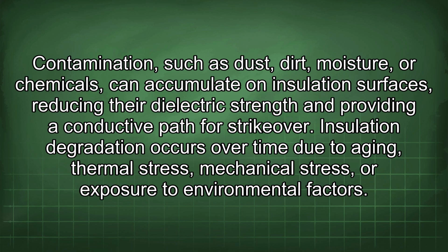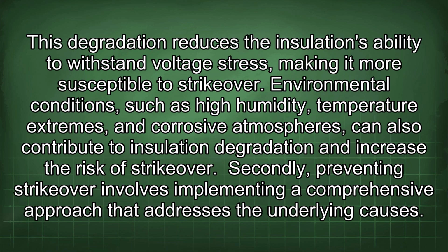conductive path for strikeover. Insulation degradation occurs over time due to aging, thermal stress, mechanical stress, or exposure to environmental factors. This degradation reduces the insulation's ability to withstand voltage stress, making it more susceptible to strikeover. Environmental conditions such as high humidity, temperature extremes, and corrosive atmospheres can also contribute to insulation degradation and increase the risk of strikeover. Secondly, preventing strikeover involves implementing a comprehensive approach that addresses the underlying causes.